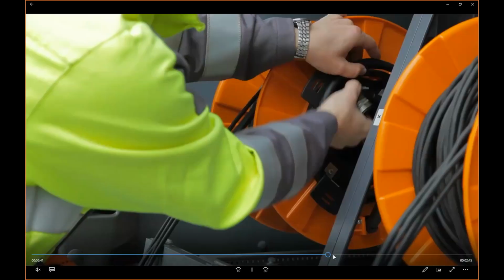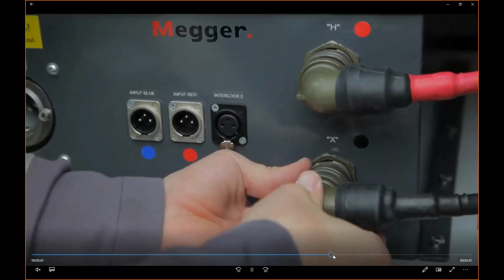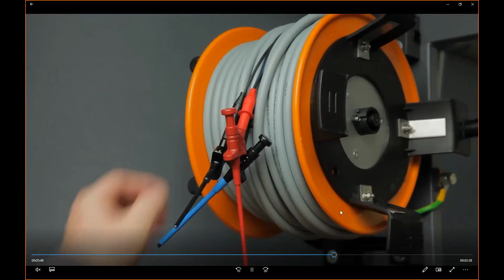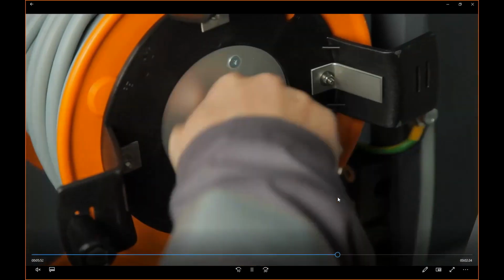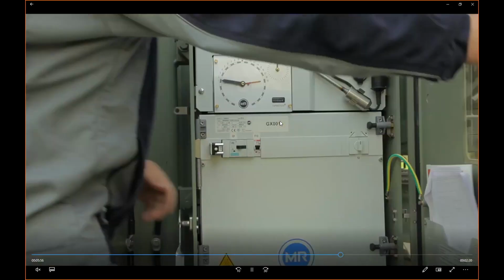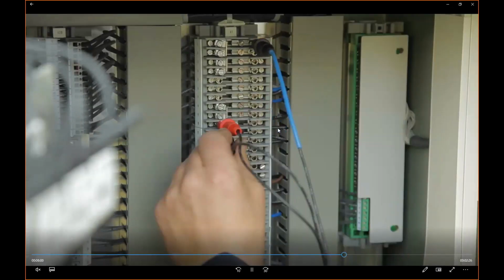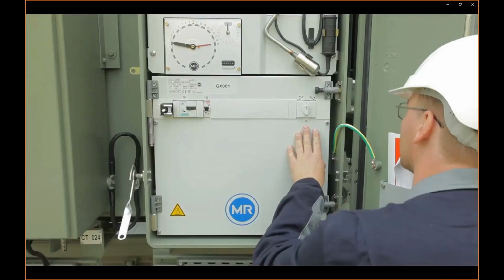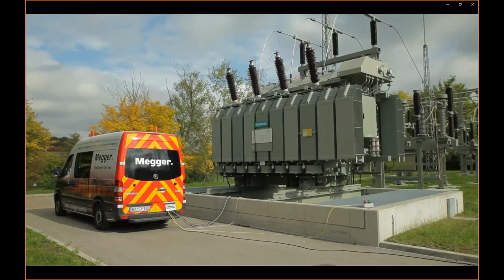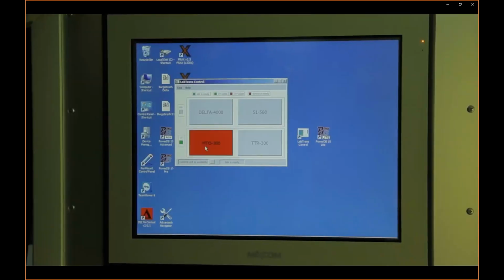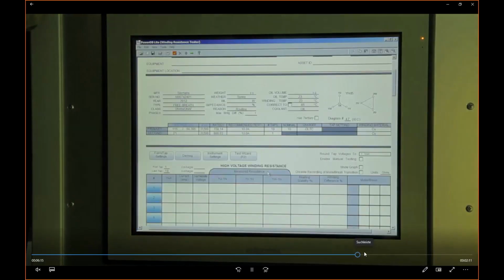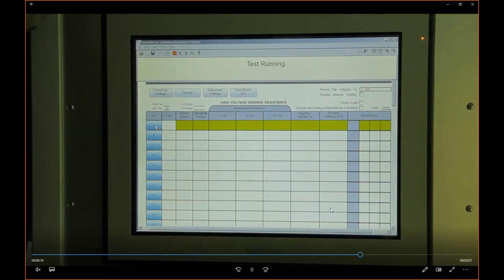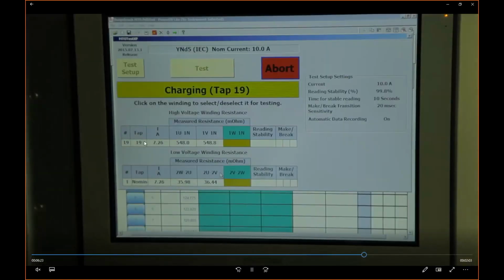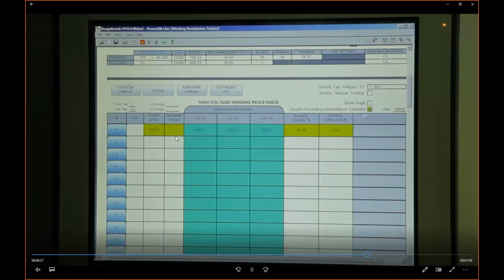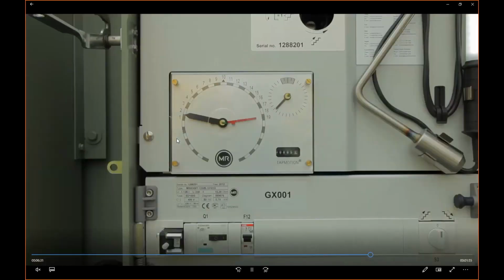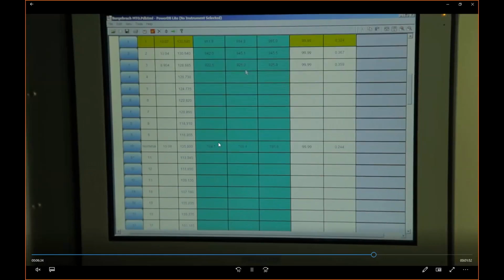And you connect the other end of the cable reel to the switch box output. If you need to connect to the control of the tap changer, you also use a particular cable reel. You connect up and down connections and power supply, and you are ready for remote control of the tap changer. So the software, or you can press the button by hand, can go through all taps and all phases. So this is an example shown for winding resistance, where you can see this is a test done at tap 19. And then when the report is formed, you can press the button, or the software can do the job for you, depending on what instrument is integrated.